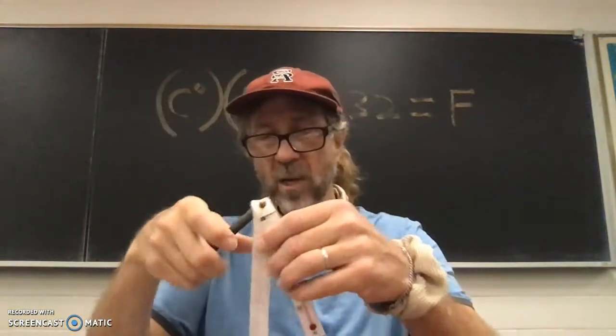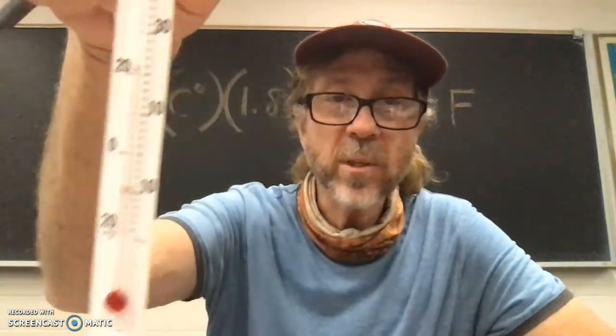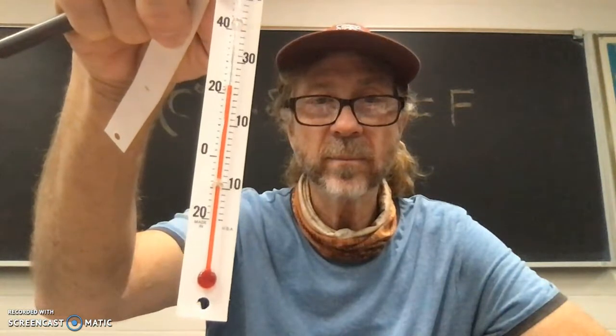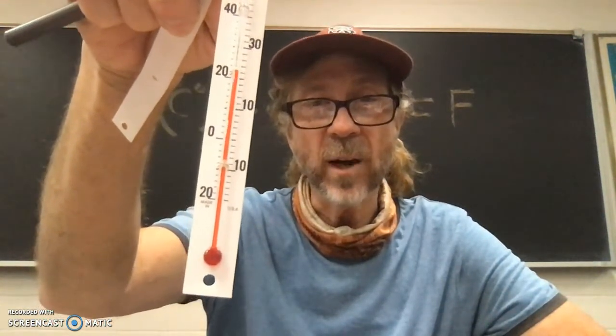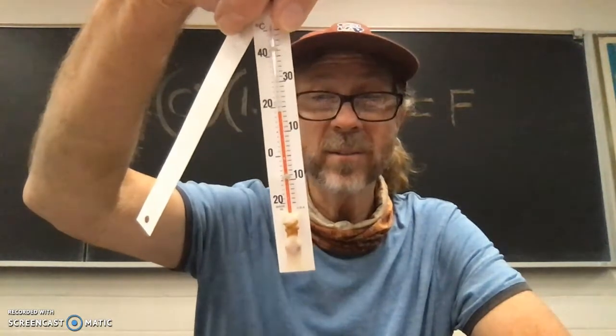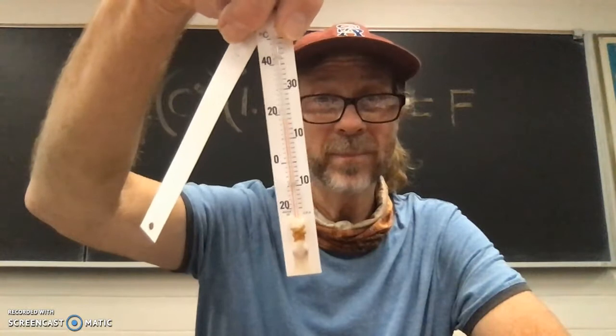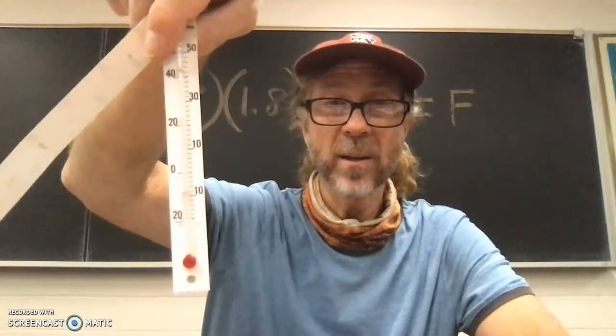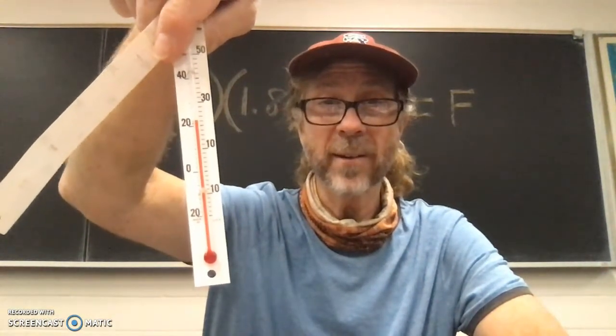Let's see what we got. First, let's take a look at the dry bulb. You can see the dry bulb right there — see what that temperature is? It's not 35. And then take a look right here — can you see the wet bulb? It's a lower temperature. Remember, these are in Celsius. Write them down and record them. There it is — that's the wet bulb, this is the dry bulb.